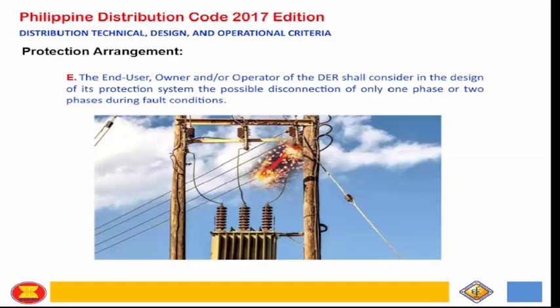And also any design with possible disconnection of only one phase, single phasing. Of course there's an impact, as mentioned earlier. Single phasing will cause unbalance in the generator, which is worse compared with unbalanced load. The unbalance is really excessive. So you are in charge of your protection. You should have negative sequence overcurrent protection coordinated with the negative sequence damage curve of the generator. It's not the responsibility of the utility or the cooperative if the line goes single phase, because that exists there.